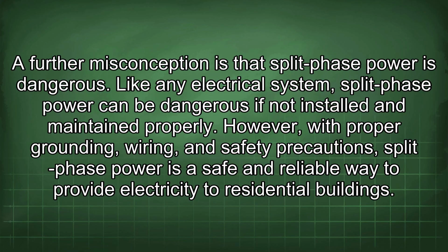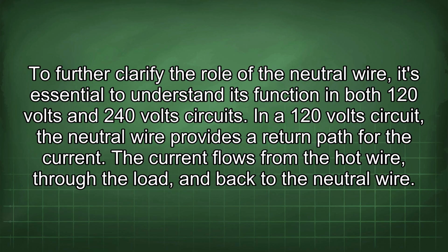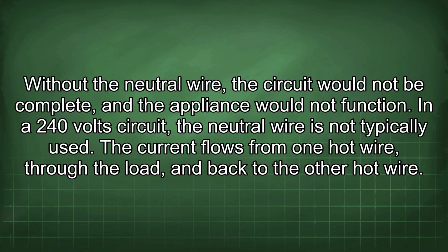residential buildings. To further clarify the role of the neutral wire, it's essential to understand its function in both 120 volt and 240 volt circuits. In a 120 volt circuit, the neutral wire provides a return path for the current. The current flows from the hot wire through the load and back to the neutral wire. Without the neutral wire, the circuit would not be complete and the appliance would not function.